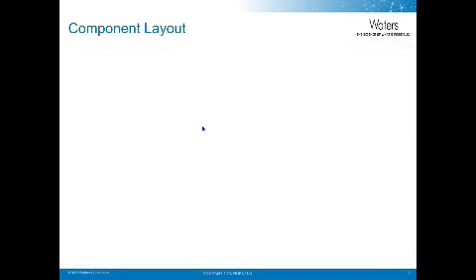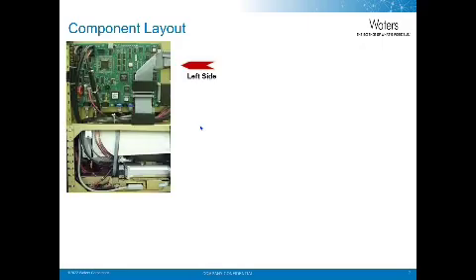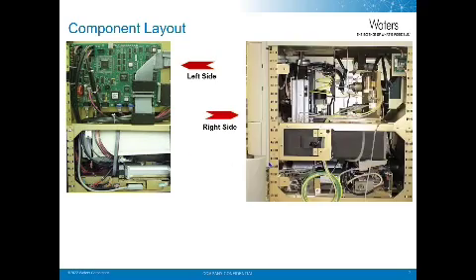Next, let's take a look at the components inside of the system. If we took off the covers and looked inside the left side of the system, we would see the CPU board shown here. Pump tray assembly is also shown down here. And in addition, you can see the cable to the CPU board shown here. If we take a look at the right-hand side without the covers, we would be able to see the injector.